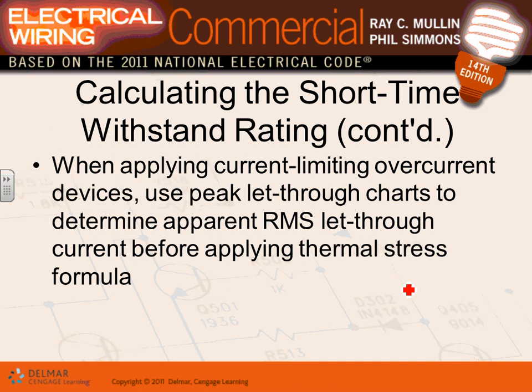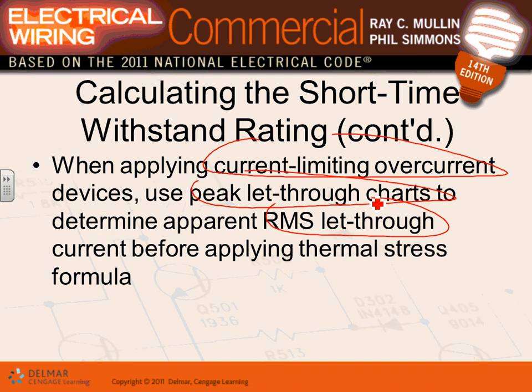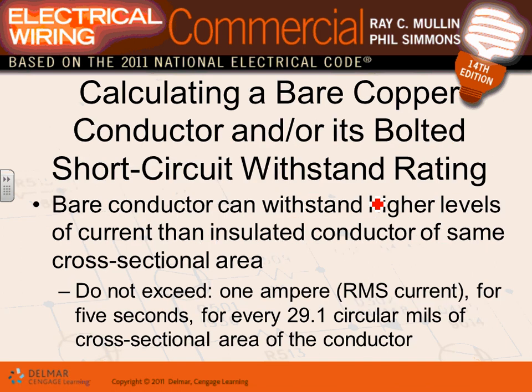Okay, if you have a current limiting fuse, I'll show you guys a current limiting fuse. The peak let-through and the RMS let-through will be used in this formula, guys, to decide how much thermal and magnetic force will be let through. The current limiting fuse is very simple. You put 100,000 amps here. For a quarter of a cycle, it drops it down to 25. That's it. It limits it. So why do we do that? When it limits it to 25, then this equipment will not be shaken and baked that much. So they use the current limiting fuse, and the RMS let-through I squared T is very small.